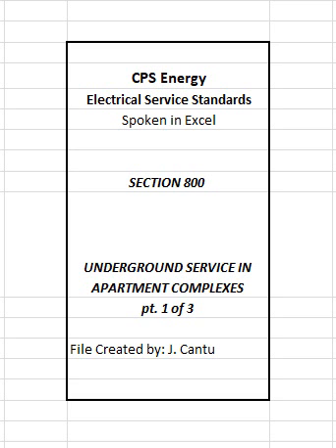803 Transformers. CPS Energy will determine the number and location of distribution transformers. Customer shall furnish space meeting all clearance and easement requirements for each transformer and shall allow it to be readily accessible by CPS Energy personnel.